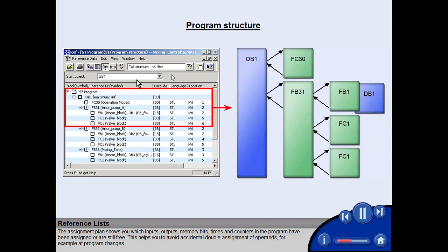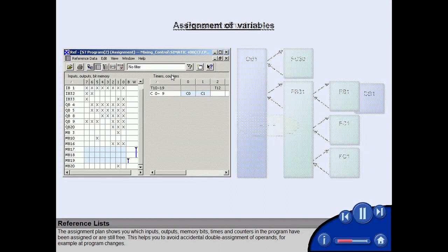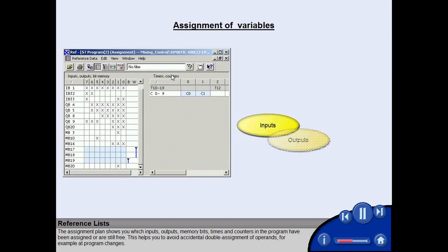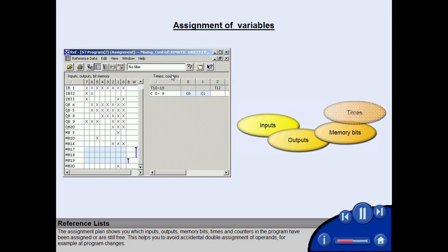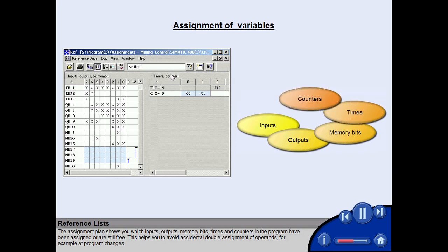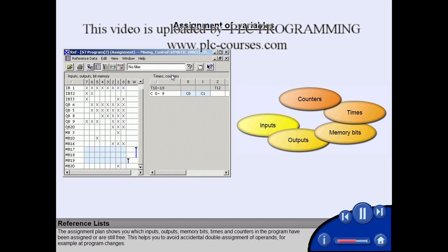The assignment plan shows you which inputs, outputs, memory bits, times, and counters in the program have been assigned or are still free. This helps you to avoid accidental double assignment of operands, for example at program changes.